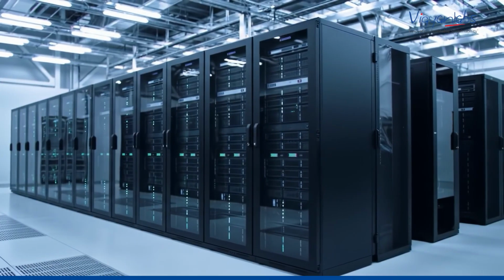We all know that training AI is much more costly than inferencing it. So is liquid cooling or air cooling suggested? Again, it depends on the density of heat. Let's look at a rack: up to 30 kVA of energy consumption in a rack, you can use liquid cooling or air cooling. Beyond 30 kVA, you probably need to use heat exchangers to take the heat out. Maybe from 30 to 40 kVA you can manage with heat exchangers and air cooling. Beyond that, I don't think this technique works; you need to use liquid cooling, with cooling distribution taking the heat directly from the chip to the outside. Today we are looking at rack densities of 60 kVA, 100 kVA. As density increases, air cooling is not good enough.